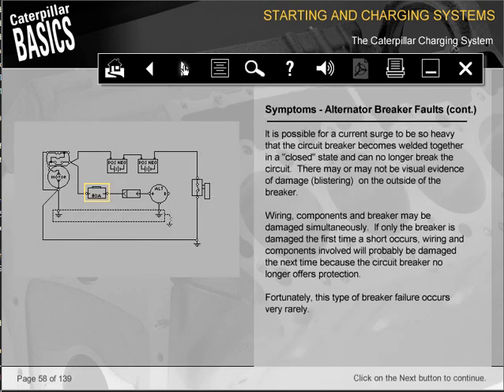It is possible for a current surge to be so heavy that the circuit breaker becomes welded together in a closed state and can no longer break the circuit. There may or may not be visual evidence of damage, blistering, on the outside of the breaker. Wiring, components, and breaker may be damaged simultaneously. If only the breaker is damaged the first time a short occurs, wiring and components involved will probably be damaged the next time because the circuit breaker no longer offers protection. Fortunately, this type of breaker failure occurs very rarely.